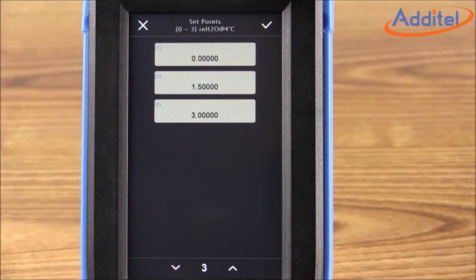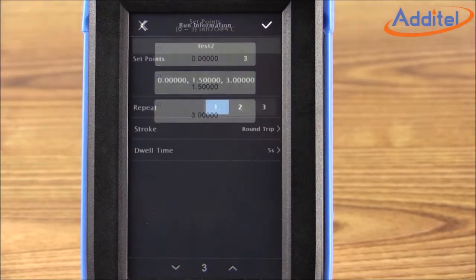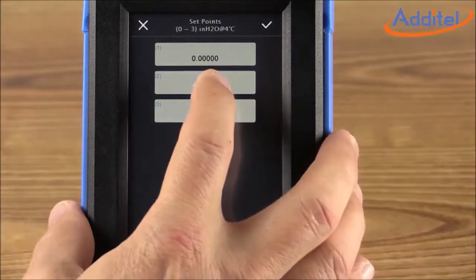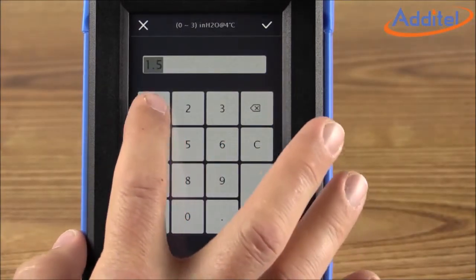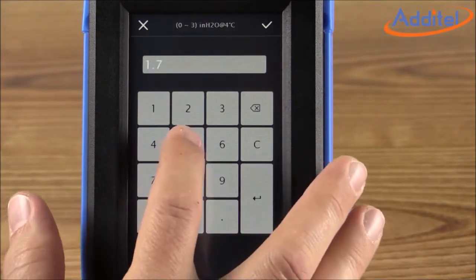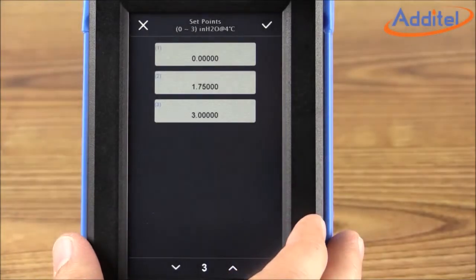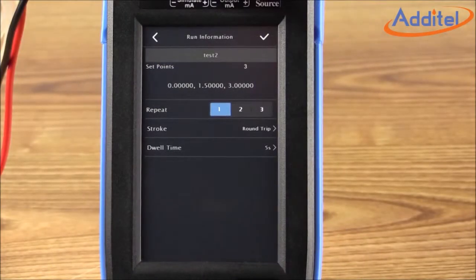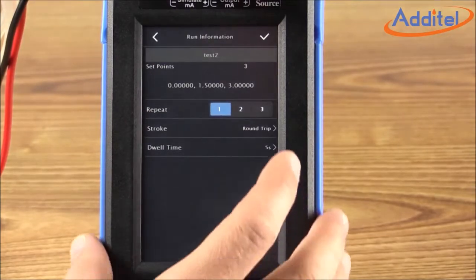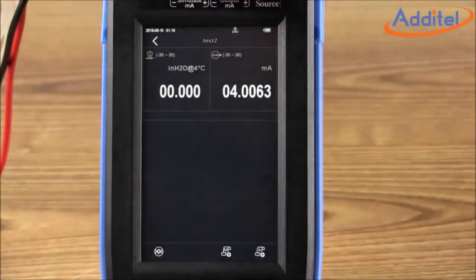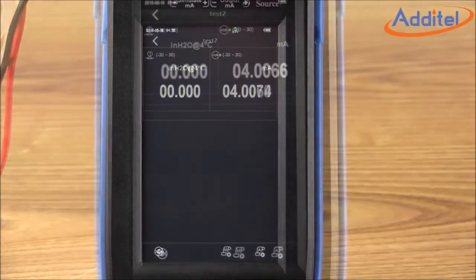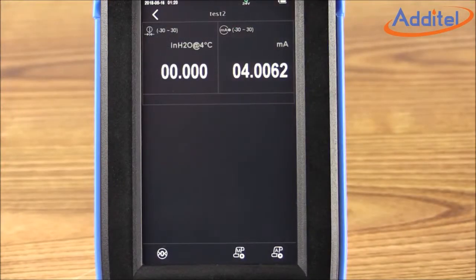Note how the ADT760 auto-adjusts the set points as you add and subtract calibration points. We can also change a single calibration point by selecting the cal point of interest and inputting a new value, such as 1.75 inches of water. Once the calibration points are configured the way we want them, select the check mark icon in the upper right corner. From this screen, we have the option of zeroing the pressure.